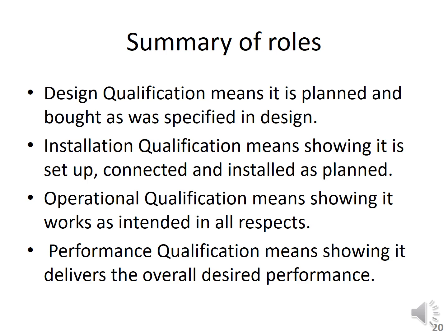OQ, the operational qualification, means showing it works as intended in all respects. And last, the performance qualification PQ means showing that it delivers the overall desired performance. It is delivering the overall desired performance or not. You are testing it and you are keeping the record of it.